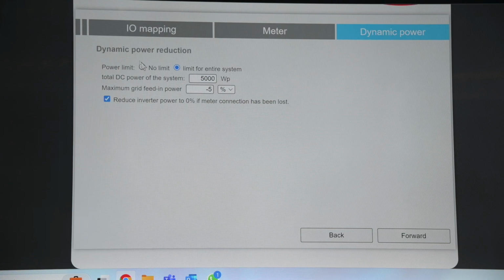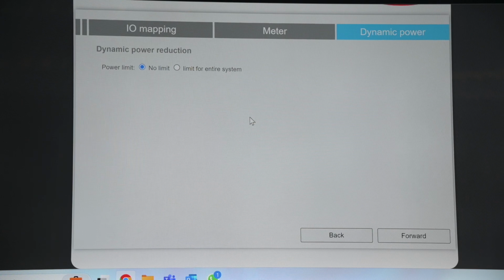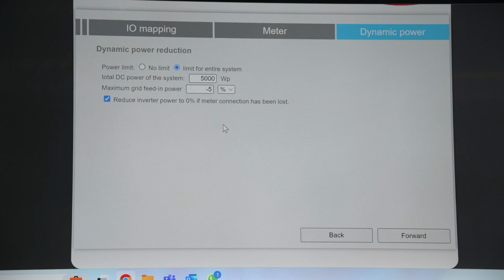Next is your dynamic power reduction. This is if we want to do zero feed-in on the system itself. If it's a grid tie operation, we'll then say we want to limit the entire system, and then we'll input the total DC power of the system itself. So for example, we've got multiple inverters that we're running at 25 kilowatt available on the system itself. We can then say we want to maximize the grid feeding power.